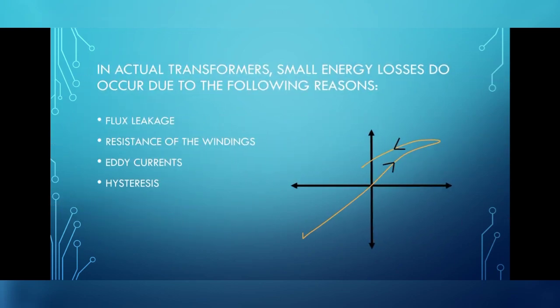No one can be 100% perfect in this world. Similarly, the transformer also has some imperfections such as energy losses. In actual transformer, small energy losses do occur due to the following reasons. Flux leakage: not all the flux in the primary winding gets transferred to the secondary winding. This occurs due to the poor design of the core or the air gap in the core. It can be reduced by winding the primary and secondary coils one over the other.